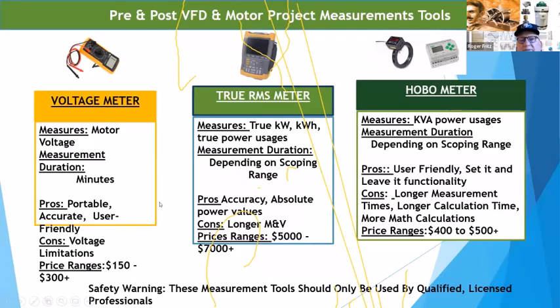This also is a tool: you can aggregate over time when the pump is running and when it isn't running, to do a calculation of what you can save in power on the VFD over time. Whether it's a pump, a fan, inlet vanes, outlet vanes, or throttling valves, you can determine what your true savings will come out to in a given application.